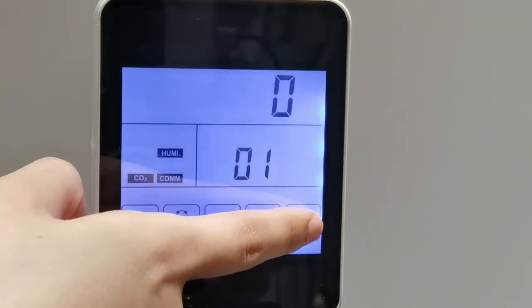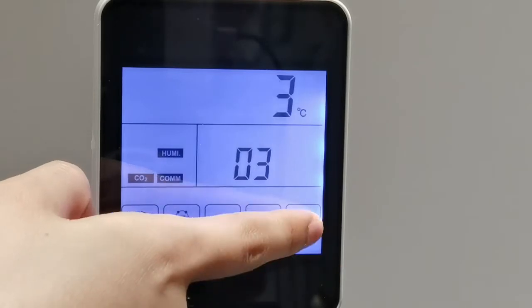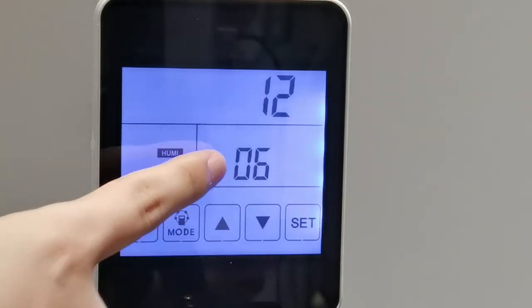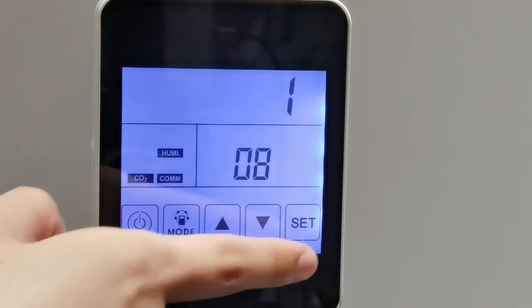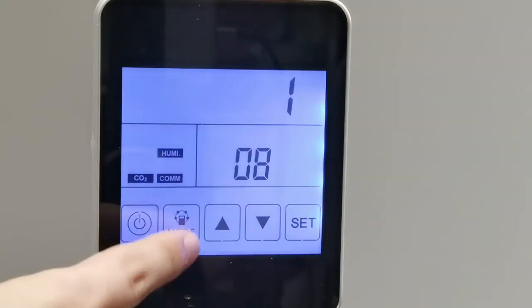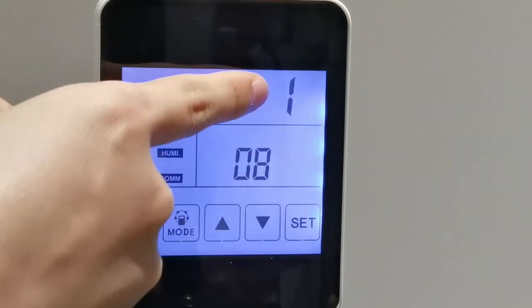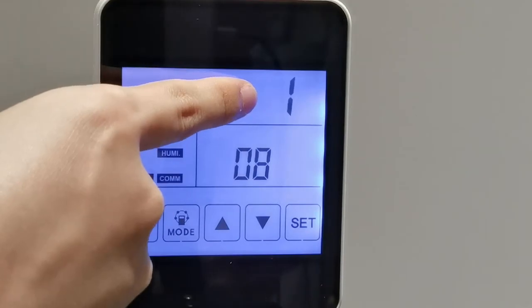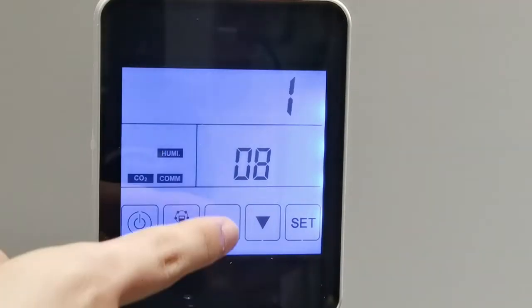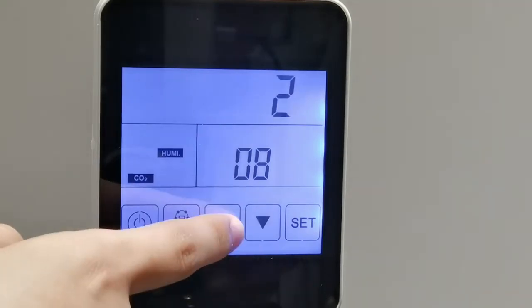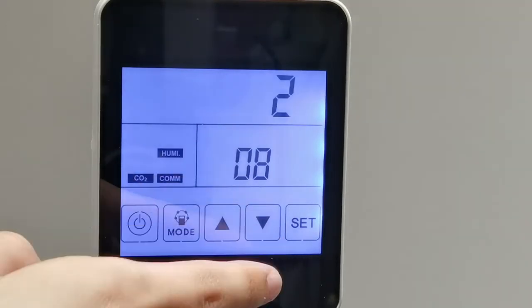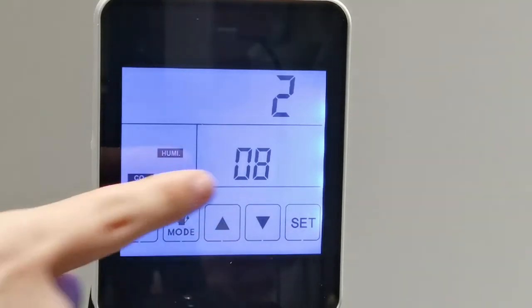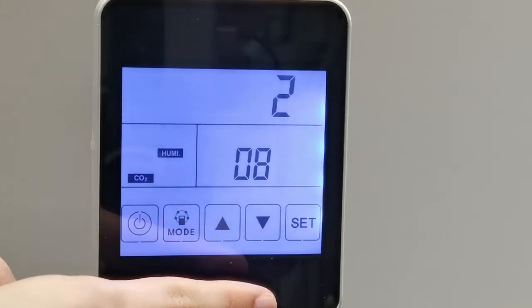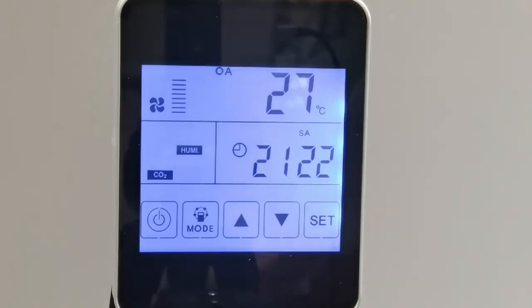The number ranges from 00 to 25. After choosing the correct parameter number, press the mode button. The parameter value will flash at the right corner. Now we can press the up and down buttons to change the value. Okay, the last step is to press the set button to save the record. Well, to make everything clear, now we will show you how to set the values one by one.